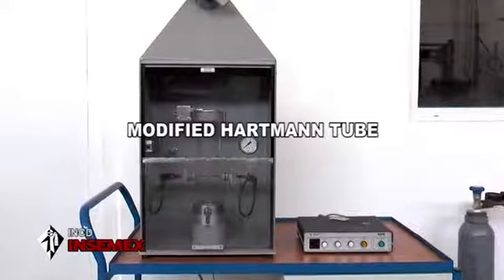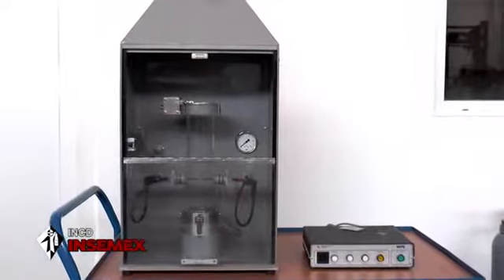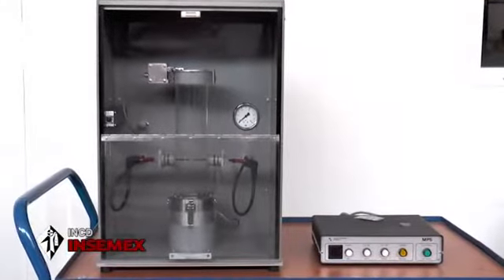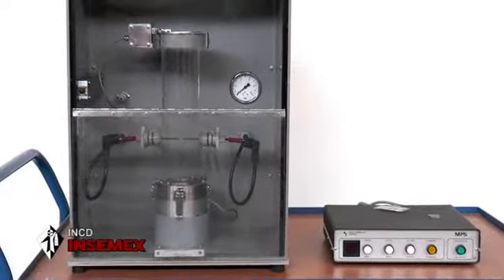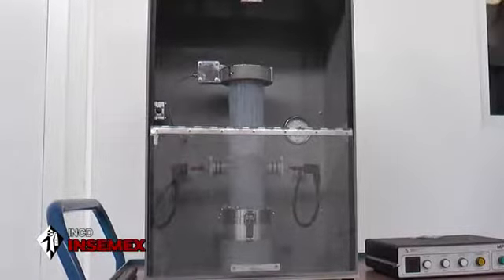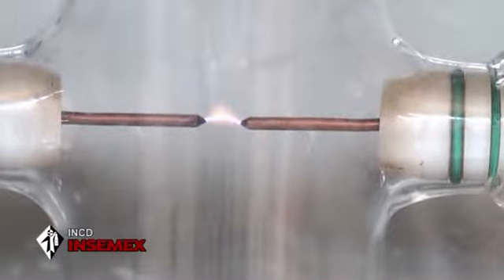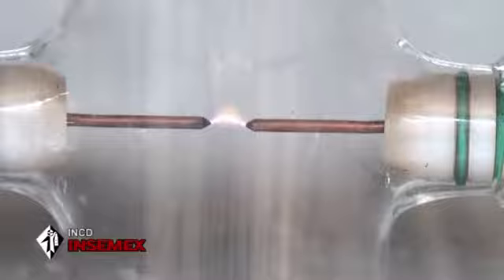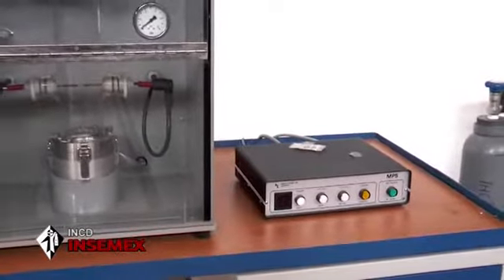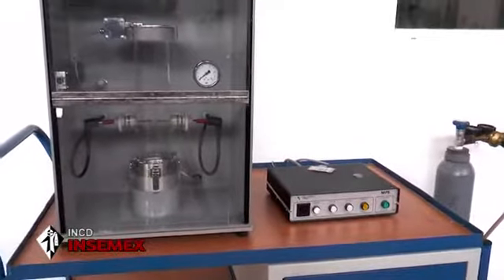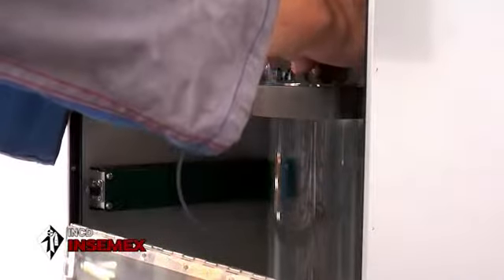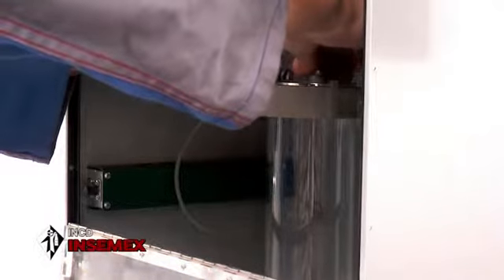Modified Hartmann tube. The modified Hartmann tube is used for the classification of the dust sample, flammable or non-flammable. Qualitative pre-testing on the behavior to explosion of the dust-air mixture. The modified Hartmann tube allows qualitative determination on the behavior to explosion of the dust-air mixture. By whirling the dust sample inside a glass tube, type Hartmann tube, igniting the mixture from a continuous source with enough energy, viewing the phenomenon and recording it using an electronic device type active flap located in the upper part of the glass tube.